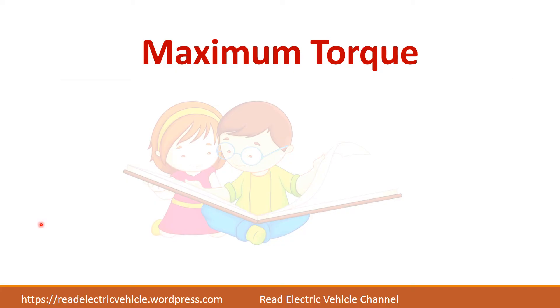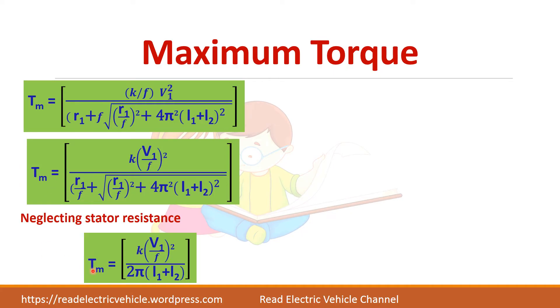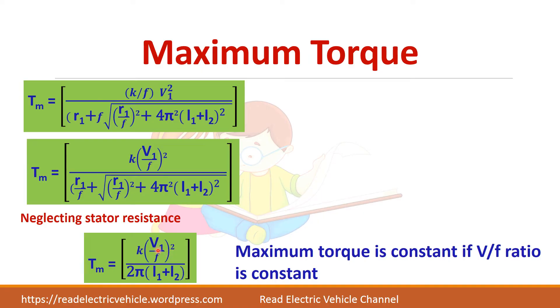Simplifying and neglecting stator resistance, the maximum torque equation becomes: T_max = K × (V1/F)² / (2π × (L1 + L2)). Since all remaining terms are constant, maximum torque is directly proportional to (V1/F)². So if the V by F ratio is kept constant, the maximum torque remains constant — this is the key advantage of V by F control.